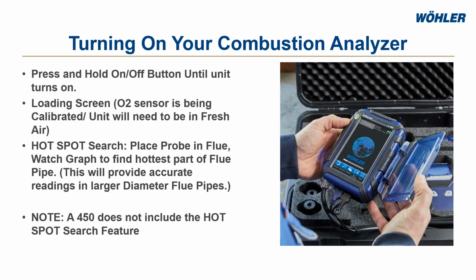At this point, when this is turning on, it's really important that you have this out in fresh air. That could be outside and outdoors, or if you can't be outdoors, making sure the probe is pulled out of the flue. You never want to start an analyzer up when your probe's in the flue, even if the furnace or boiler is turned off, it doesn't matter. You want to make sure that this is in completely clean air. That way you get a good calibration.